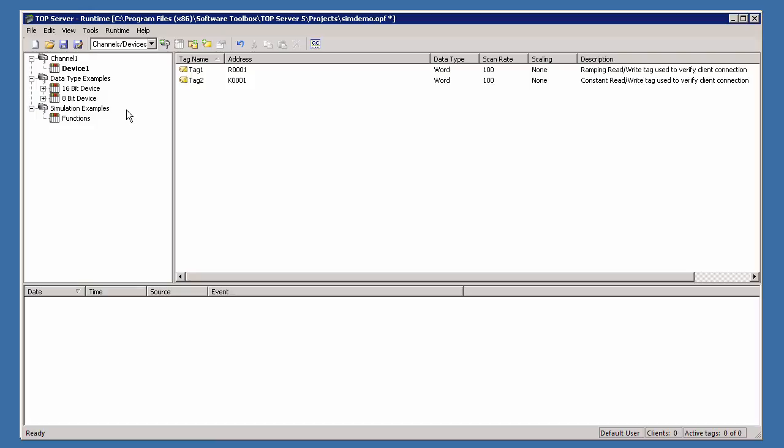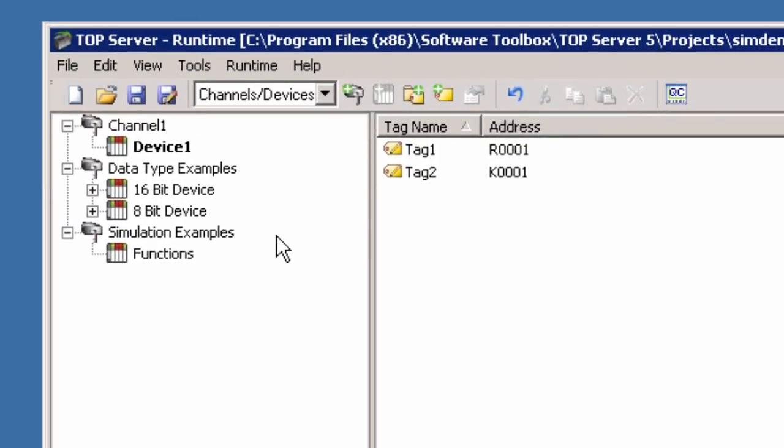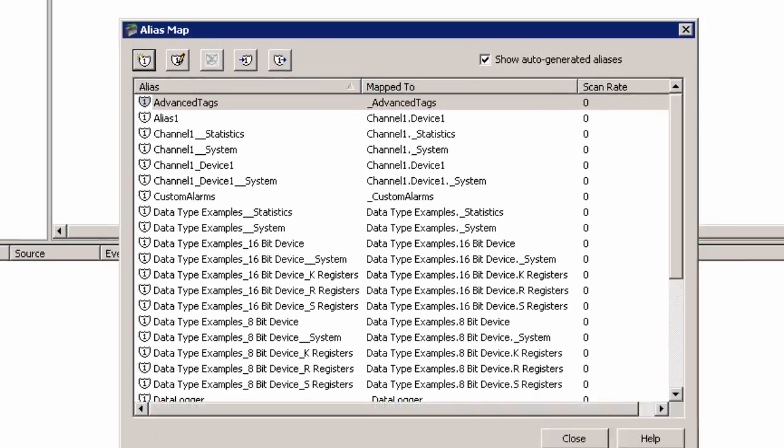Aliases are necessary in the TopServer because Wonderware does not recognize the ChannelName.DeviceName syntax in the topic name. If you are familiar with setting up topic names in other DDE servers, setting up an alias name in the TopServer is our equivalent of that step in the setup process. To do this in the TopServer, click on Edit Alias Map.